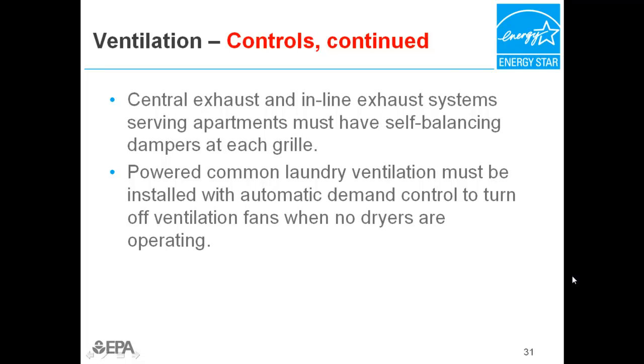Ventilation serving common laundry rooms must be installed with automatic demand control to turn off ventilation fans when no dryers are operating. This can significantly reduce energy consumption, as this reduces both electricity consumed by the ventilation fans and the thermal loss from the continual and unnecessary ventilation of this space.